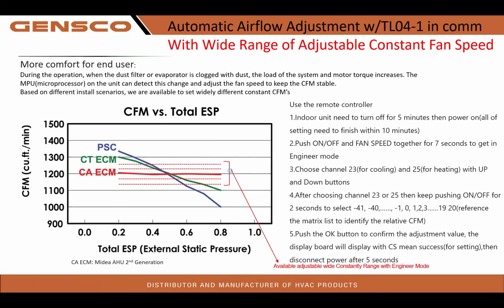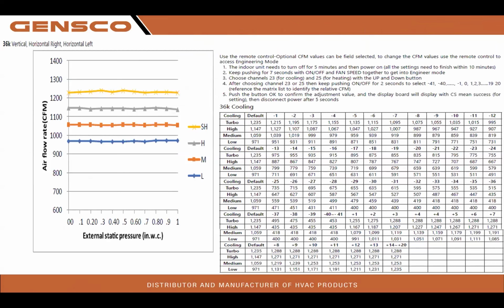hitter. Automatic airflow adjustments on the TL041 stat in communication mode with a wide range of adjustable constant fan speeds: low, medium, high, turbo. Notice our constant CFM stays depending on static pressure. We can go into advanced settings with the remote control that does come with the equipment. It is for maintenance and engineering purposes only, and we can do very specific airflow adjustments if needed. But I can tell you right out of the box, since I built 5 of these, it is not needed.